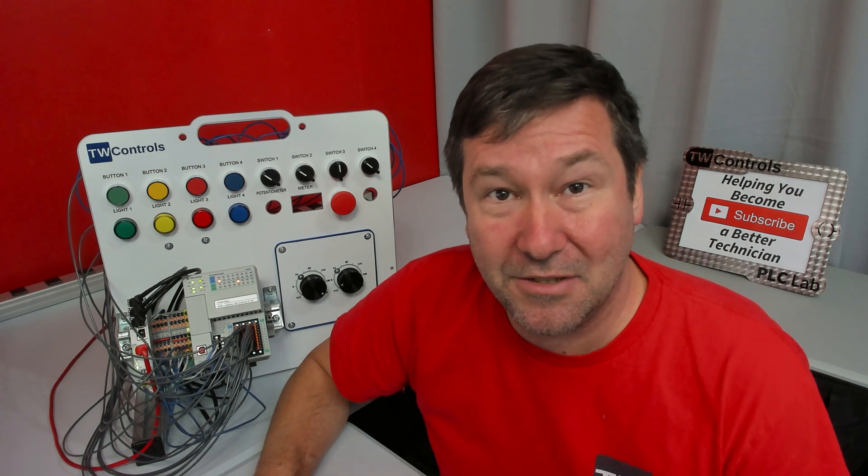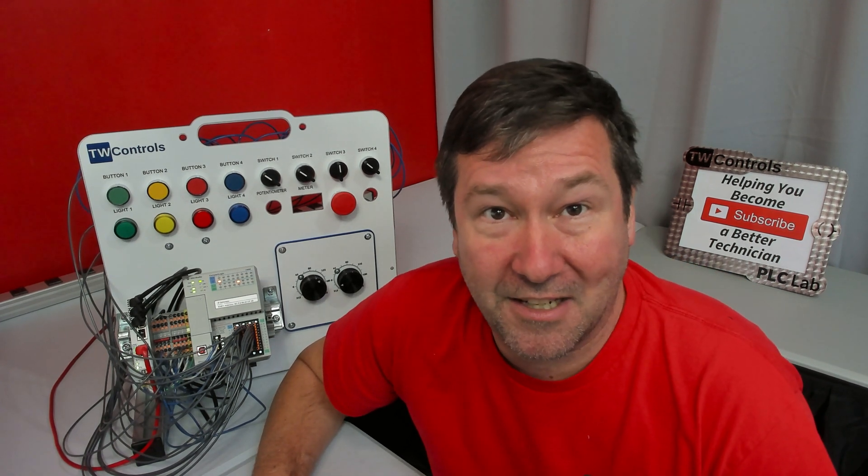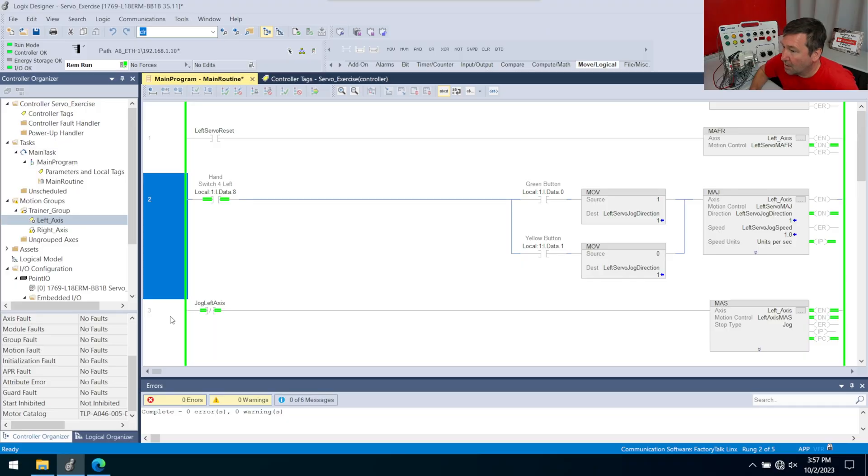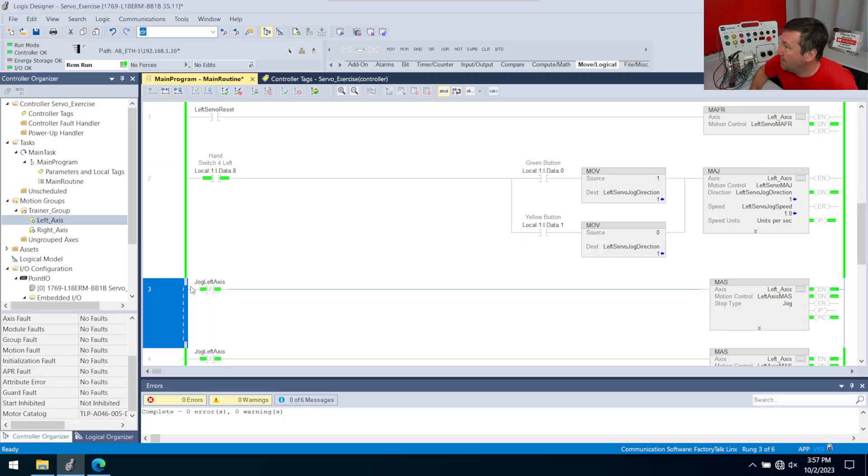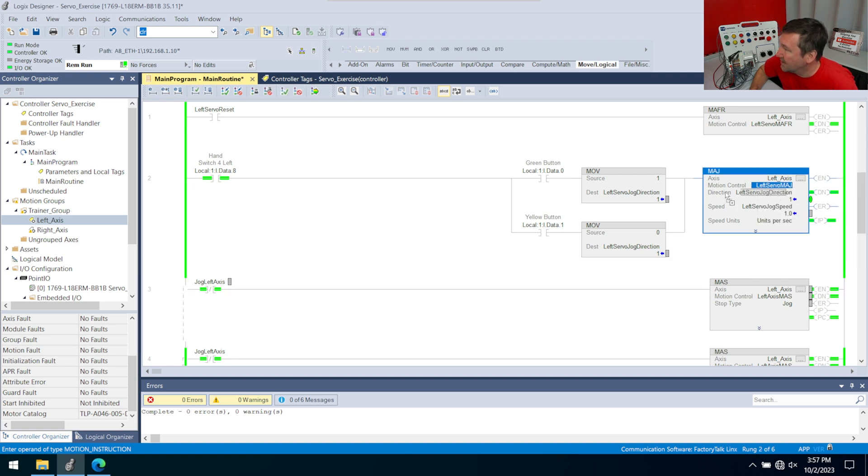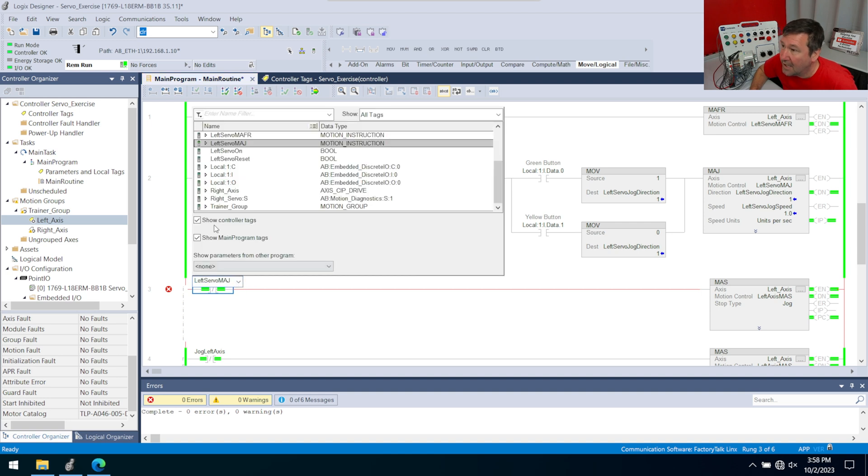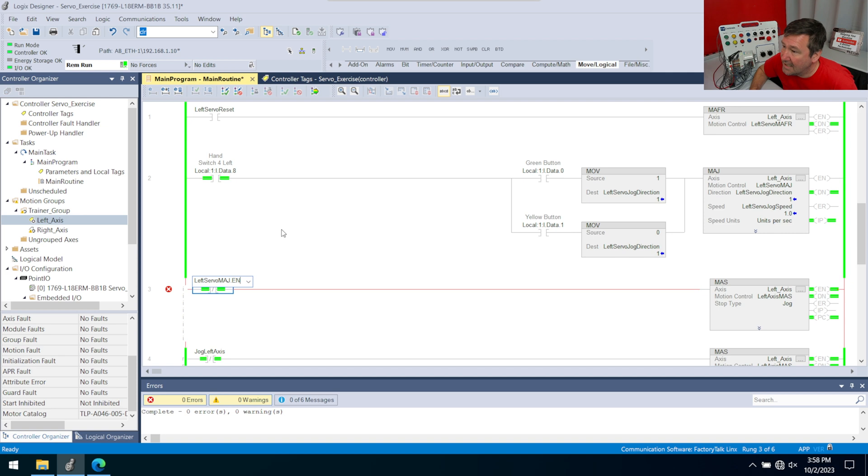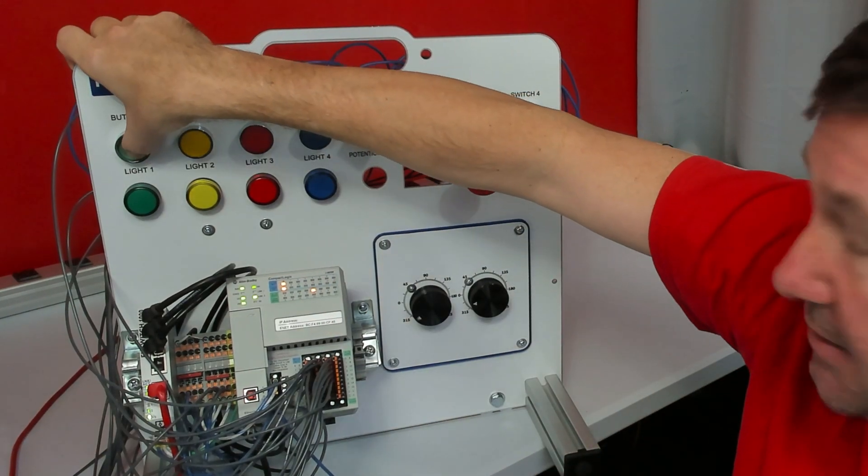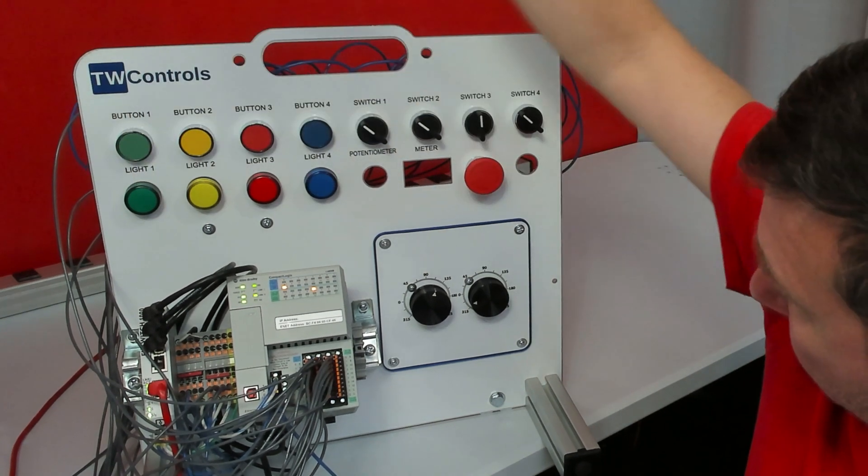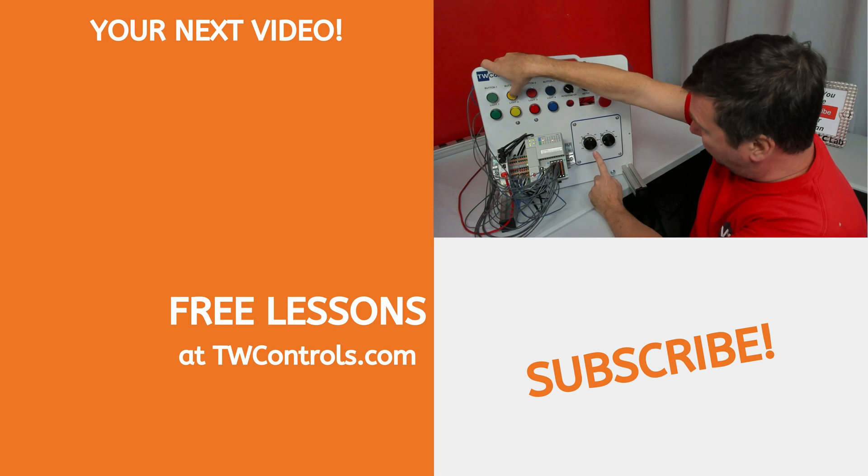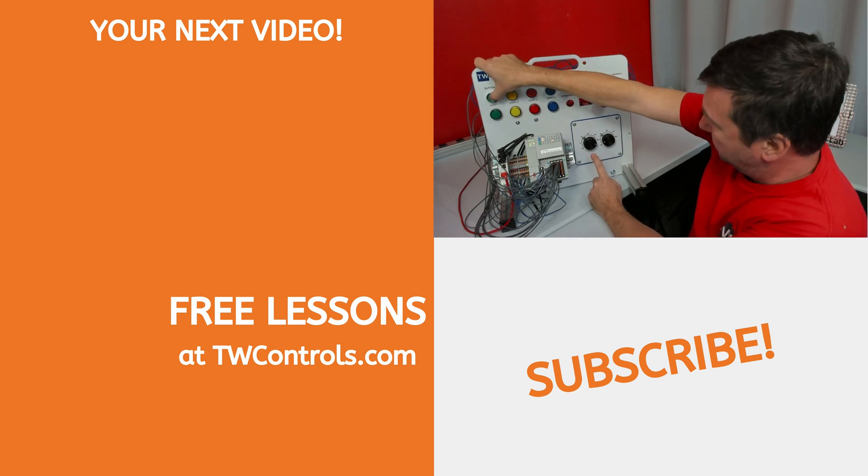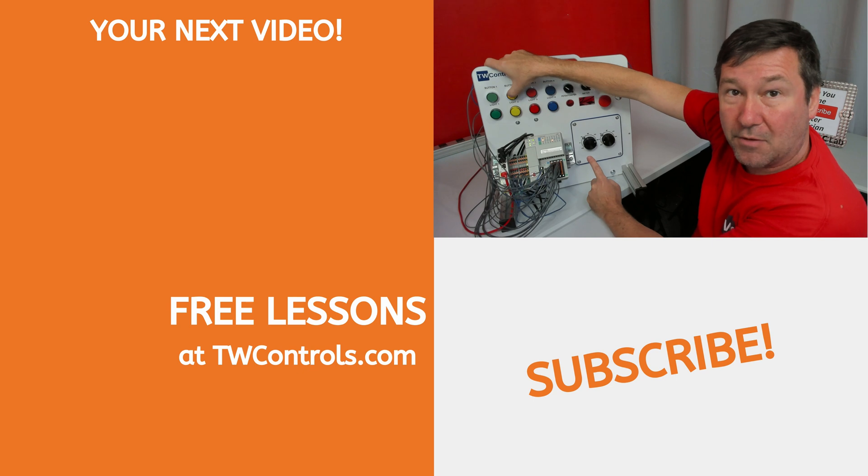Since we want the servo to stop whenever we let off the button or we make that rung false, we can actually use the EN of that motion axis jog instruction to do our stop command. So we'll start a rung edit on our motion axis stop command. This left servo MAJ instruction, that's what actually has all these bits in it. So if we click it, we can drag it down here. We're going to get a red X because we've got to go further into our arrows. But we click there, we're going to hit the arrow, and we want this EN right here. We'll finalize that. Now we press our green button. That would enable it. We let off of it, and that stops it. Now if I press my yellow, it goes the other way. So now we have where we can jog forward and reverse.